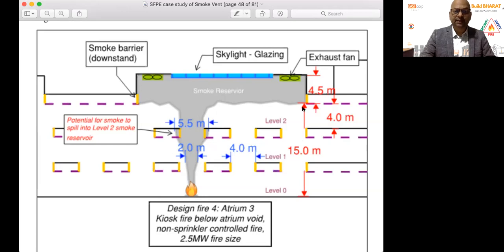How do you separate it? By providing a sprinkler system here, either with a glass partition on this side or that side. You provide a sprinkler system such that it activates and creates a shield, so the smoke and heat don't pass to the adjoining area - it stays confined to the atrium area. You also create negative pressure by activating the exhaust fan to take the smoke out.